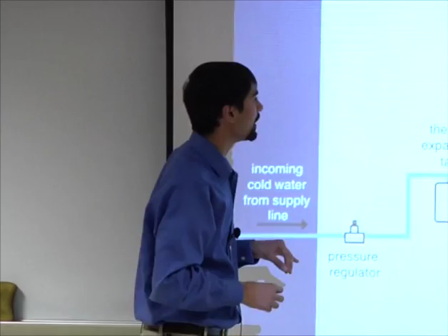But turbine-based water meters are only precise down to 0.5 GPM. If you only consume water at less than 0.5 GPM, you can actually use water without the meter ever moving. You can steal water in a way by moving it at such a low rate that the meter never turns. In this case, because this goes down to 0.1 GPM, you can detect those small fluctuations and small consumption. Now we're getting to a point where low-flow shower heads, shower fixtures, and toilets use less than 0.5 GPM, and traditional water meters won't detect that if used in isolation. So the pressure-based approach gives you the smaller changes.